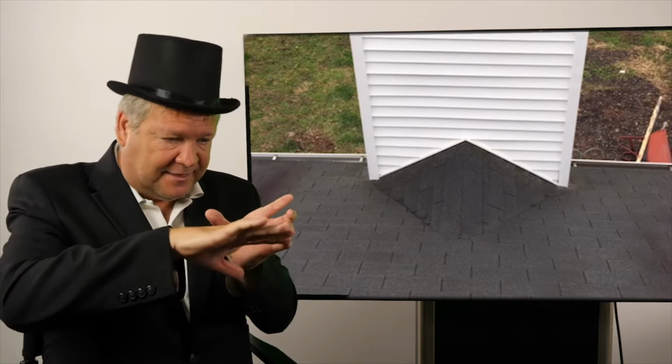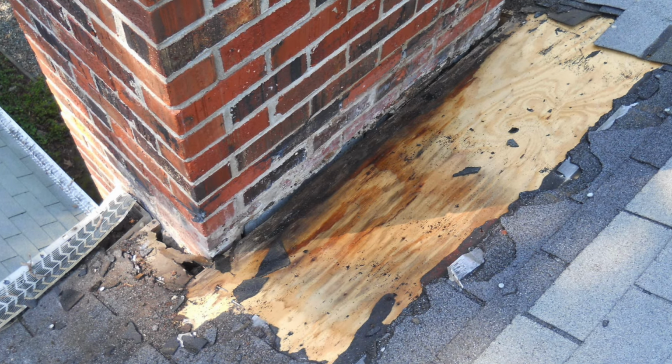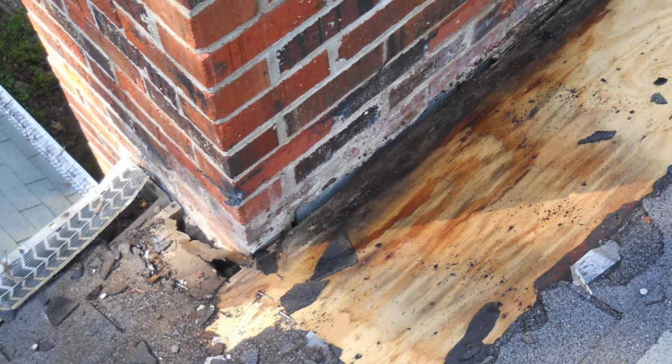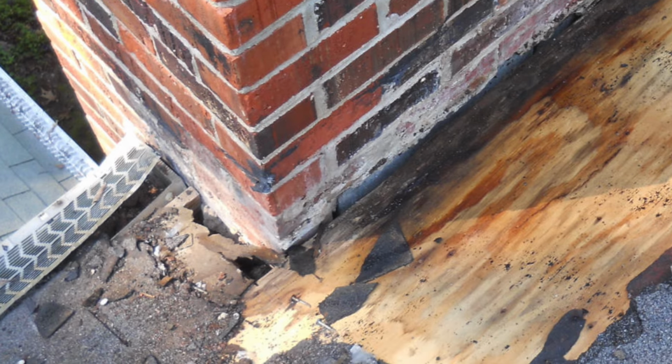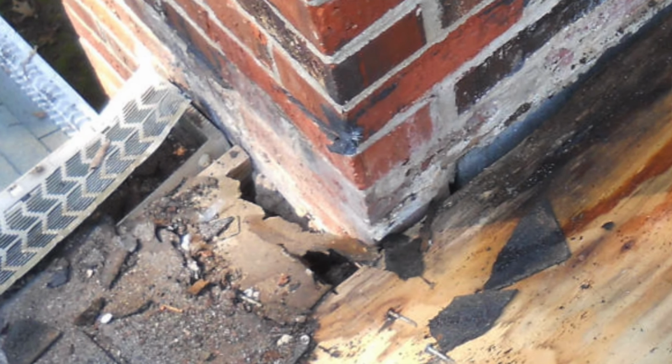Building codes require a 2-inch clearance to combustible materials around the exterior of the chimney where it passes through the roof. This clearance protects the structure from the elevated temperatures that can radiate through the chimney walls. When roofing is installed, this 2-inch gap must not be filled with combustible material.